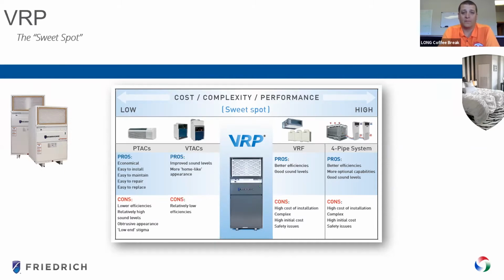On the other side of the chart, you have the VRF and 4-pipe systems. These are generally considered high-end systems that provide very precise comfort cooling and very high efficiencies. The downsides of these systems generally are the high cost of installation, the complexity to make sure that the system's operating properly, and the high initial cost. So you're going to end up paying a little bit more on the front side for those efficiencies and the benefits. That's where Friedrich came up with the VRP unit. We're trying to marry these two things, where you're still maintaining your economical cost and ease of install while having higher efficiencies and better sound levels to provide a more comfortable space for the customer.